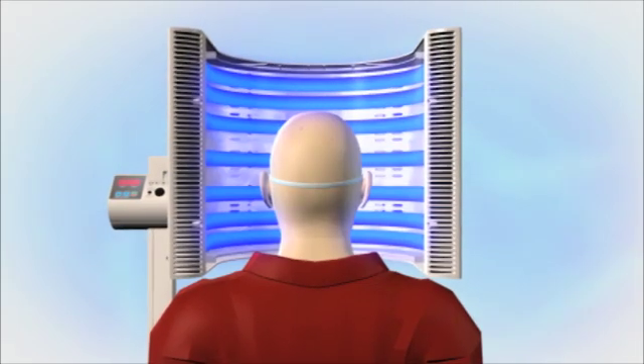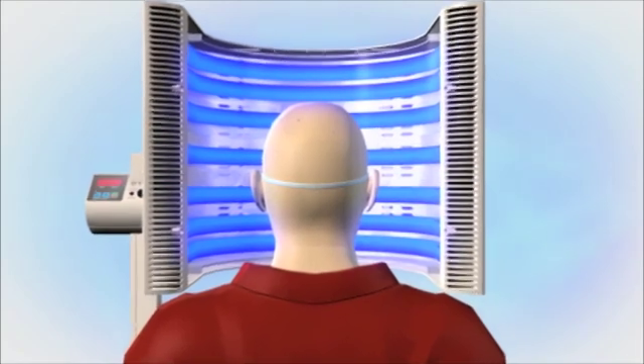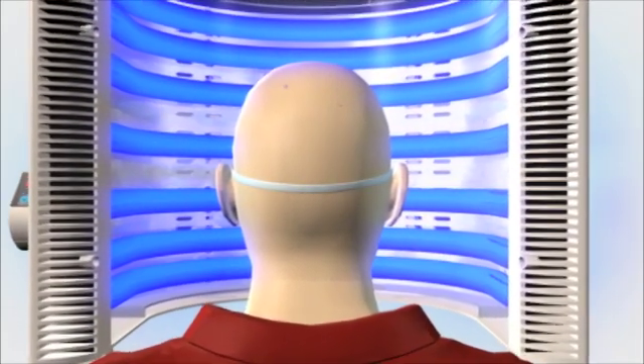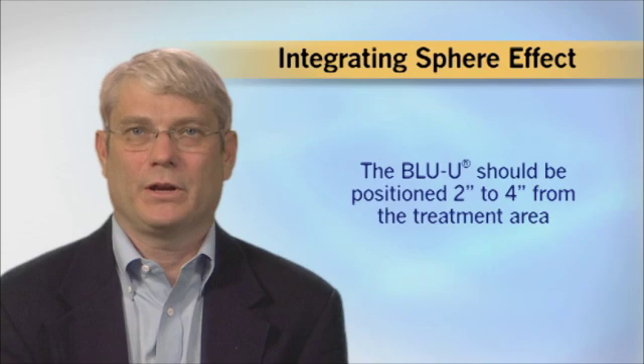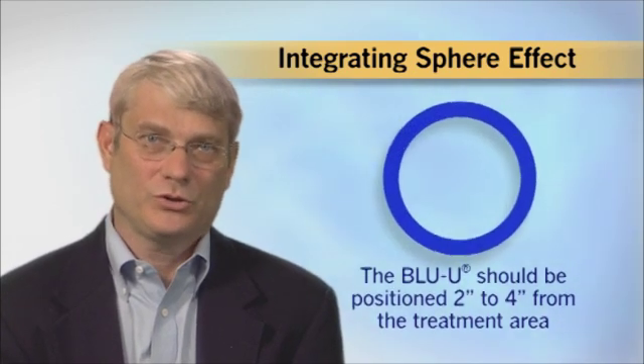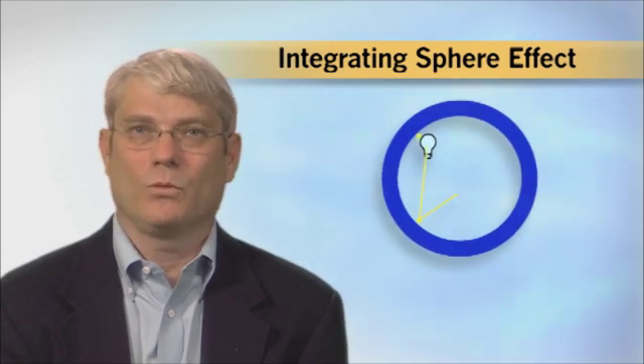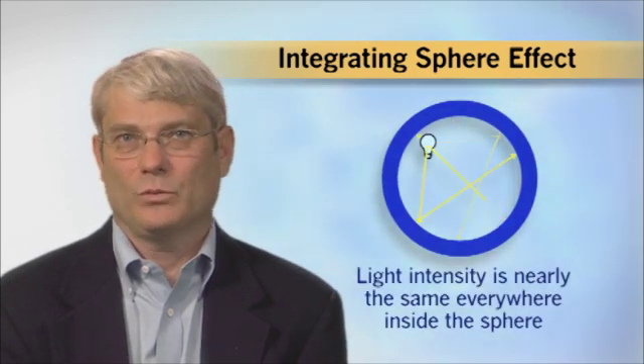What we really did was design a very tall BLU-U and then fold it over at the top and bottom, like folding a letter to get it into a smaller envelope. Now, while we had a consistent light dose from ear to ear, we found that the light dose could vary significantly with changes in distance. To mitigate this, we took advantage of a phenomenon known as the integrating sphere effect: if a light source is enclosed in a sphere with highly reflecting walls, the light intensity will be nearly the same everywhere inside the sphere.